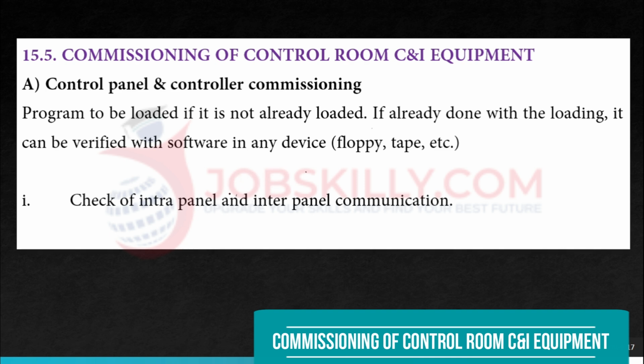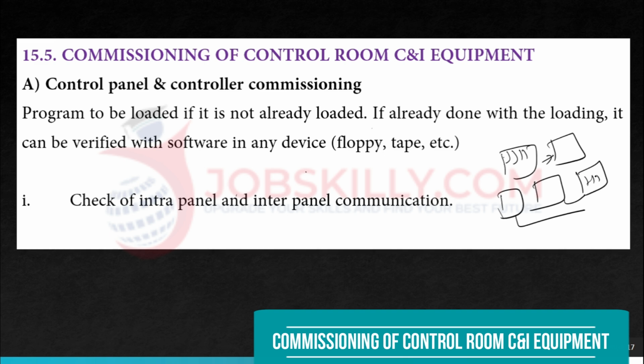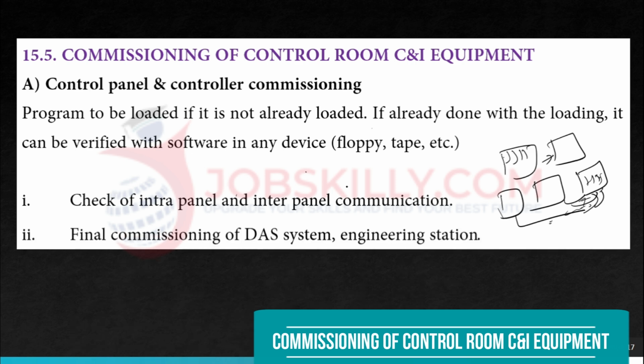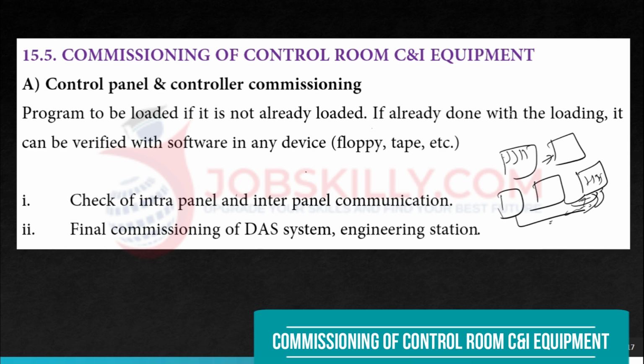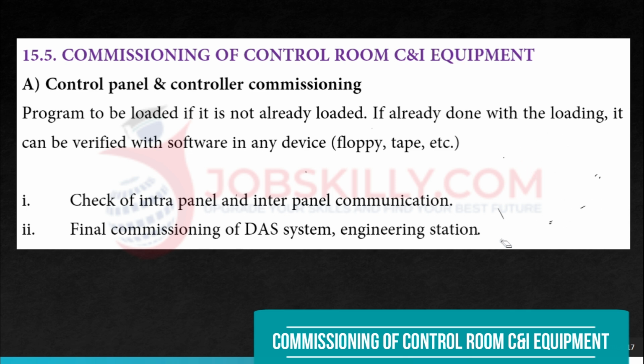Check the intra-panel and inter-panel communication, panel to panel communication and inside the panel. Suppose we are installing the marshalling panel here, we have to lay the cable up to the HIS panel. These are the communication cables we have to check. Then the final commissioning of the DAS system engineering station. Before we learned that HIS will be in two parts: one is the engineering station, one is the operating station. So we will see commissioning of this engineering station, and we have to commission the operating station also.